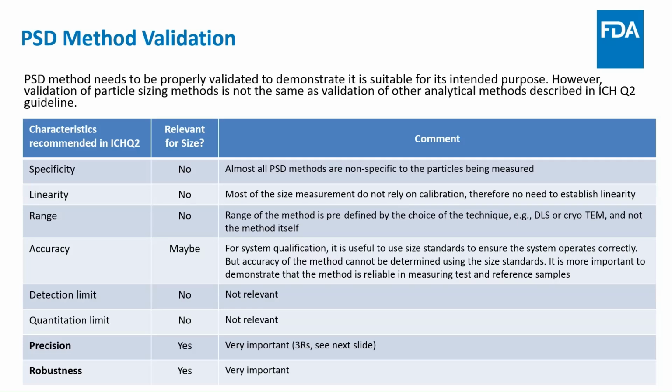In my years of experience in the lab, operating dynamic light scattering and laser diffraction, I've not seen the instrument fail in a single situation. So instruments are actually designed very robust. I'm trusting that if the company is doing that qualification every day, it's very unlikely they will see out of spec results due to an instrument issue. So this is something to keep in mind. It's something you can look at, but you don't need to overly emphasize the accuracy part.